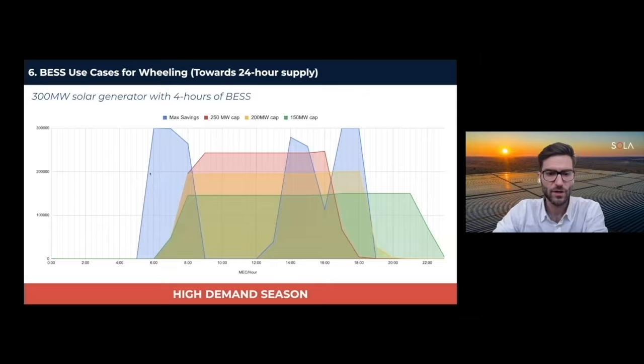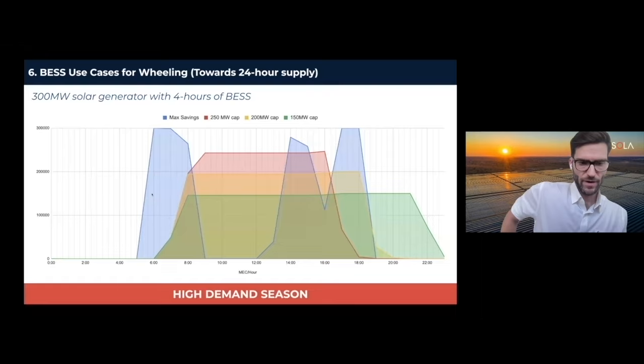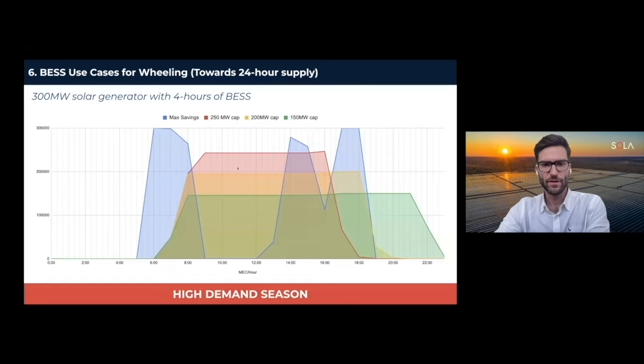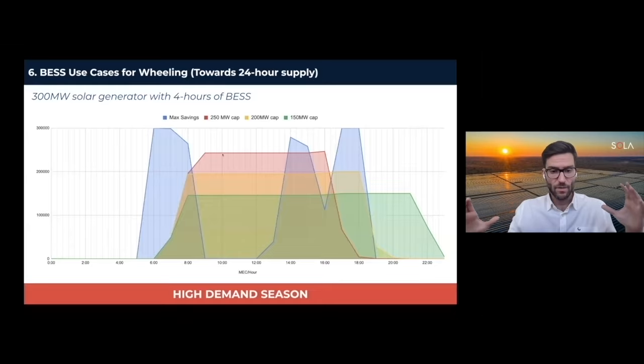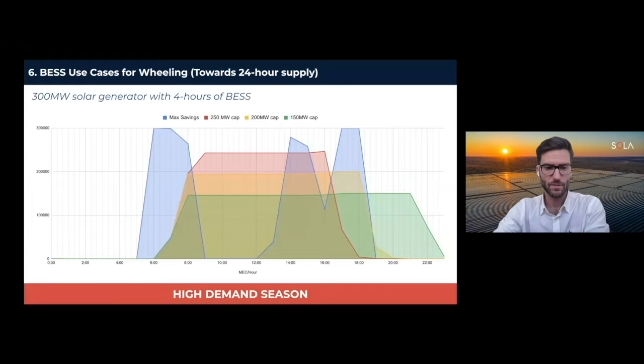Now, this blue shape is actually the maximum savings model that we looked at earlier. So this is targeting the morning peak. All the solar power in the day is being drawn down to charge the battery. And then once that battery is full, we start to discharge that solar again. And then in the evening, when the peak comes, we discharge that battery to get the evening peak. So that's why you get this funny squiggly line for that maximum savings, which is very different to these more baseload type generation profiles that we're illustrating, where we just start to spread them out as much as we can.